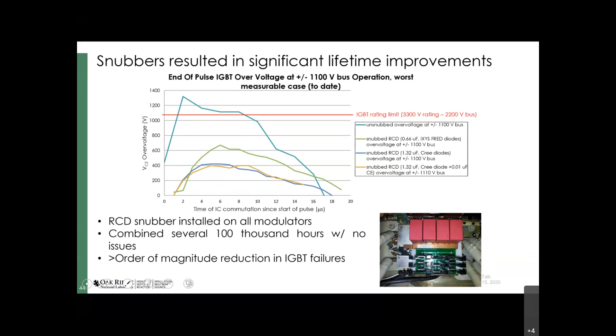We evaluated a variety of different diodes, and some of those results are shown down here. You can see that we were able to reduce the overvoltage by a factor of 3 in the case of the silicon carbide diodes that we utilize here. Ever since we've installed these, we've had no real problem with overvoltage on IGBTs, and that's after several hundred thousand hours of operation.